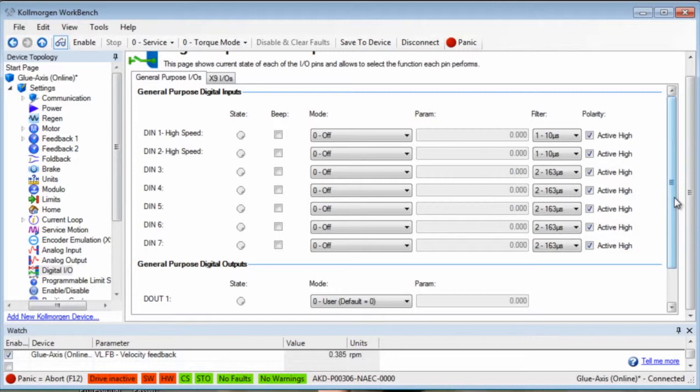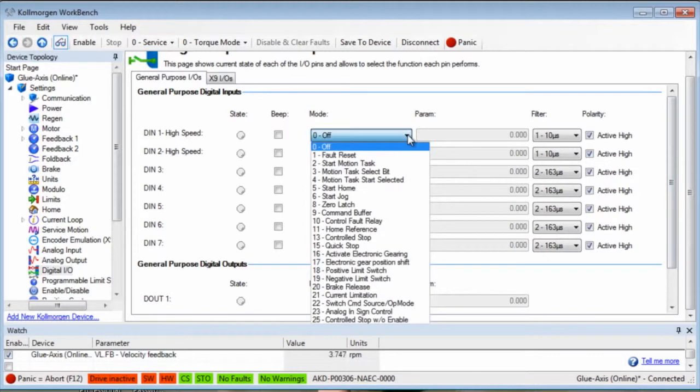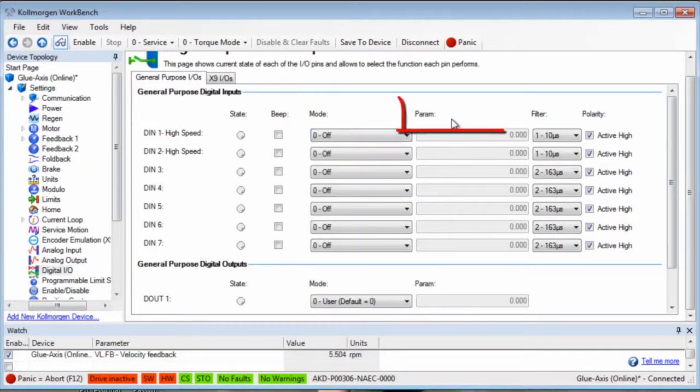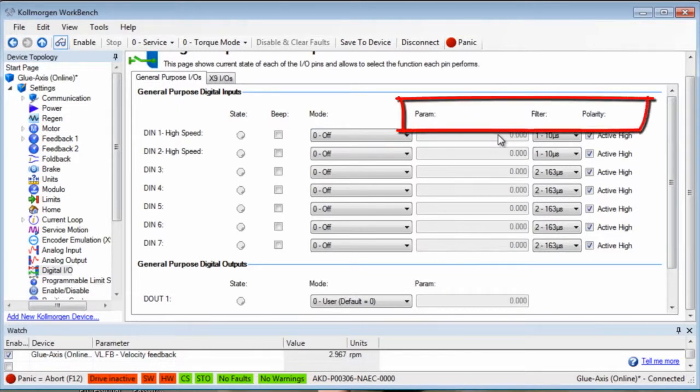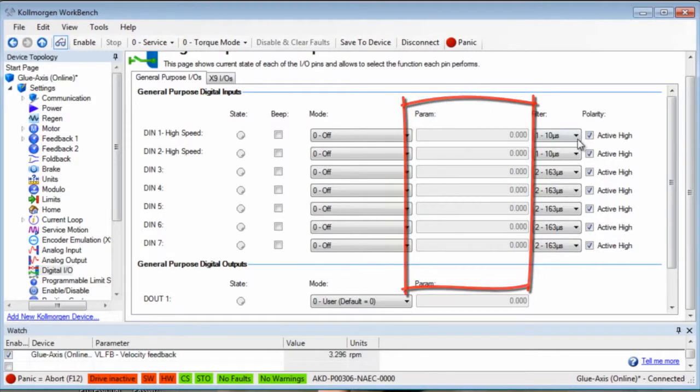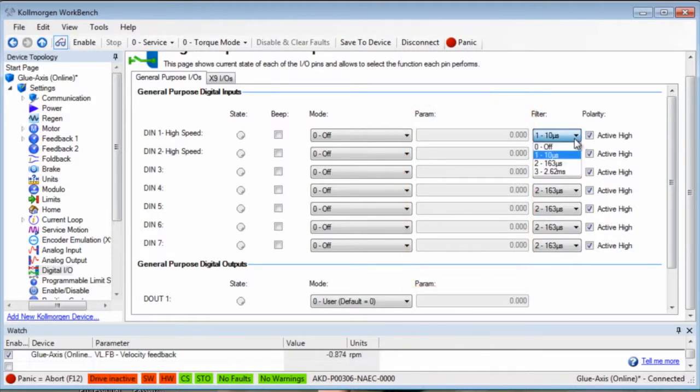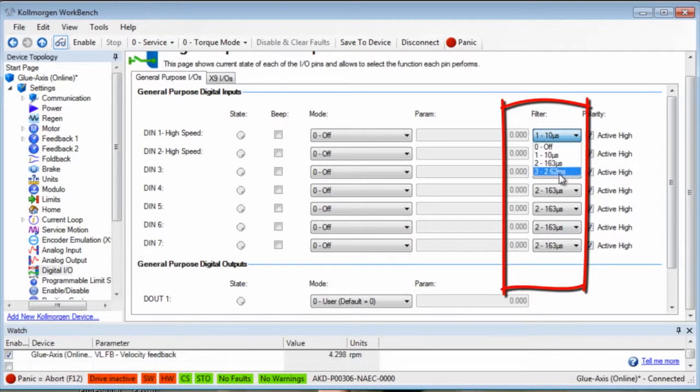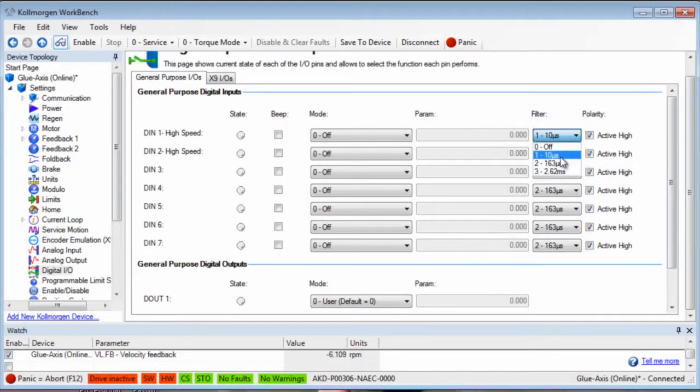Each programmable input can be set to one of many different mode types. Because there are so many, I'm going to take a few on which to focus. Things that are common to all inputs are the param column, filter, and polarity. The param will hold the specific value depending on the mode selected. Filter allows the inputs to be controlled to prevent double triggering if the signal should bounce, such as a mechanical switch might do.